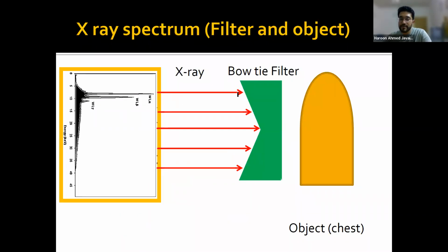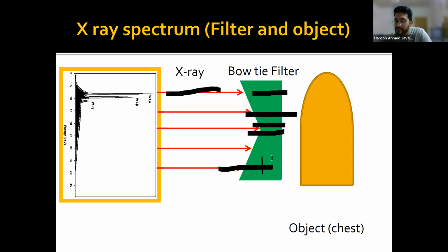So over here, this is the same concept again. If it's a very low energy wave, we don't need it because it'll be absorbed. It won't produce the image. So we'll use these ones. So the filter over here is lower. And then very high is going to be dangerous to the patient, so we want to block these off as well. That's basically what it's saying.